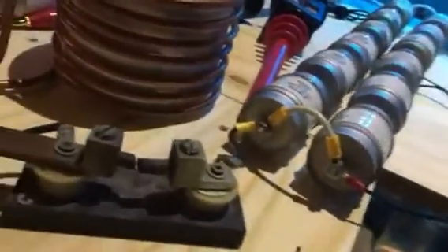So I'll show you what's going on here in just a second. The anomaly here is that with it actually discharging and the power backflowing, the input goes down while it's being loaded and discharging through the GDT. It draws 2 amps to 2.5 amps at mains voltage, 120 volts. While it's arcing and discharging, it's drawn about 1.5 amps.